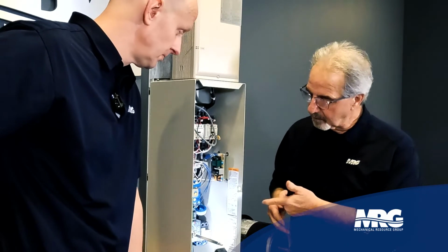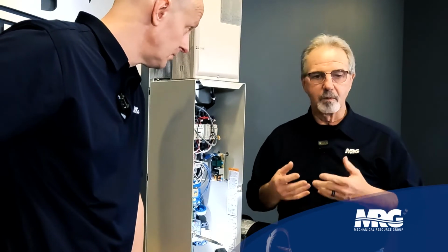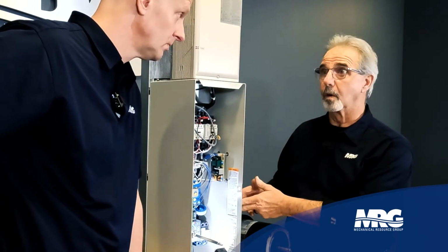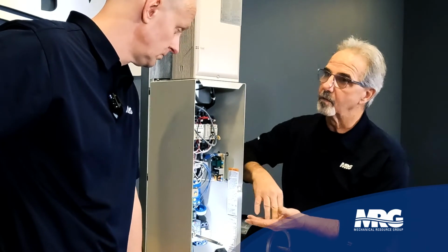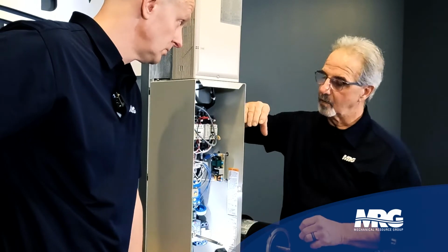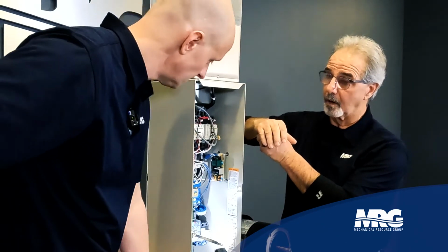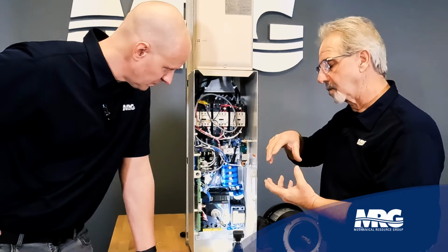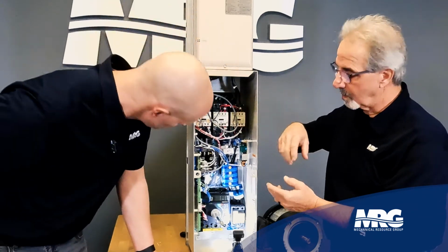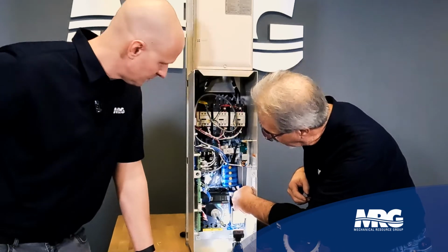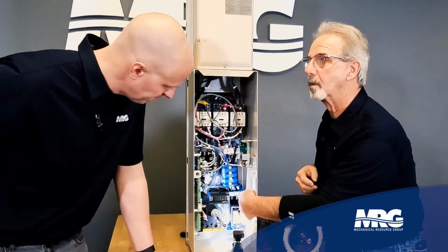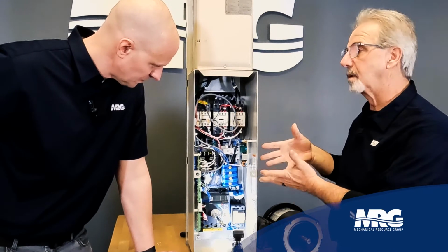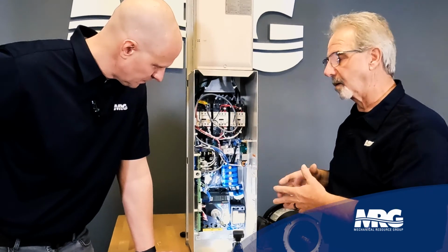So on this particular application, all you really have to do is the output of the drive is actually connected to an output mechanical overload. So really all you have to do is you lift those three leads, you slide the CoolBLUE cores on, which is this device here. And then what you do is you go ahead on each individual wire, mount the CoolBLUE cores. Okay. And then you just reattach that. We put this system here in about 15 minutes.